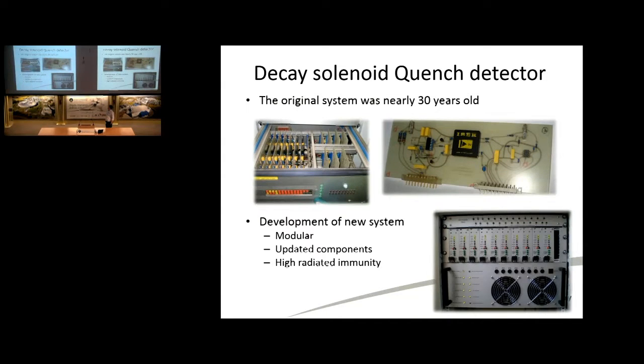This isolation amplifier provides galvanic isolation between the quench detector and the magnet itself, so that when the magnet does quench, because it will quench, the quench detector doesn't stop that. It means that the voltages on this side can come up to about 1,000 volts, but the voltages on this side will stay below 10 volts. So this isolation amplifier is working quite hard.